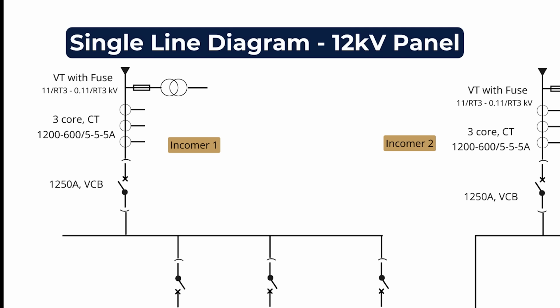So this is the panel. Now it is called an incomer because we are accepting the supply that is coming in from, let's say, a substation or maybe any other panel. And once the supply enters, we have a voltage transformer connected in parallel to the system. And to that we have a fuse also connected, which helps us to protect the VT in case of abnormal conditions. And this is a single core PT, 11 kV by root 3, and the output voltage is 0.11 kV by root 3. That's the potential transformer. I'll show you the detailed nameplate of this when we go to the panel.